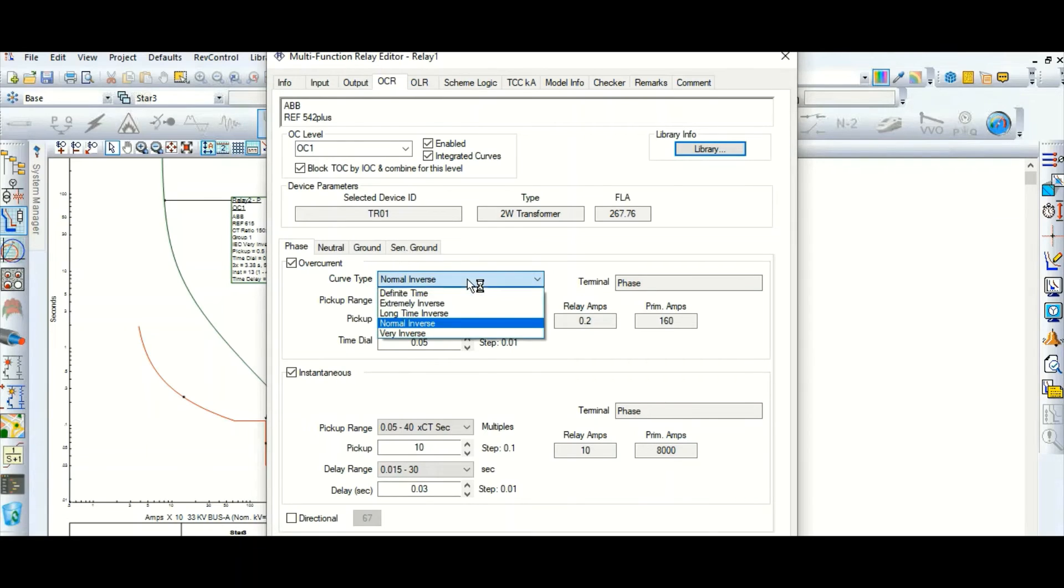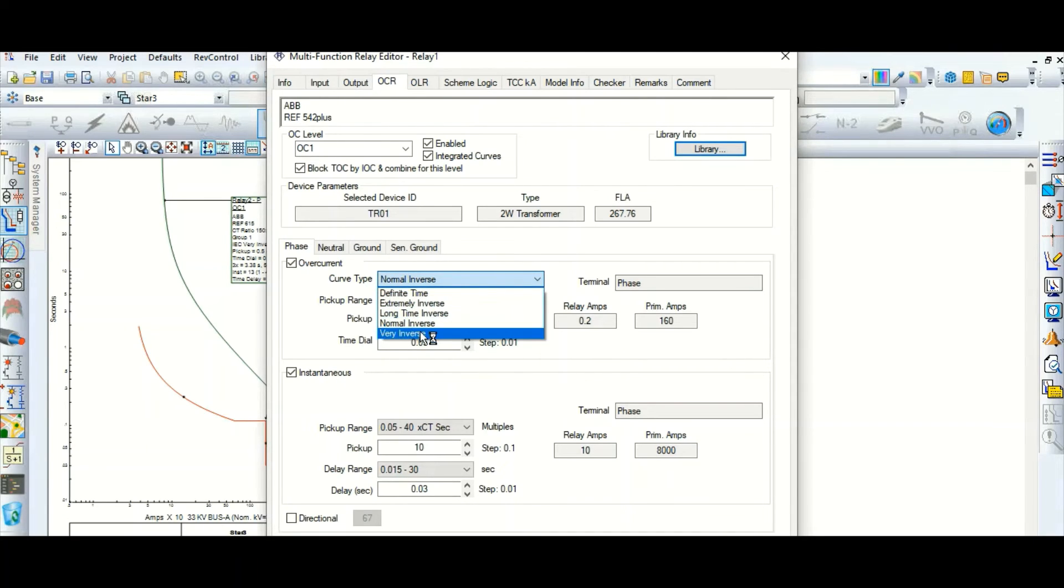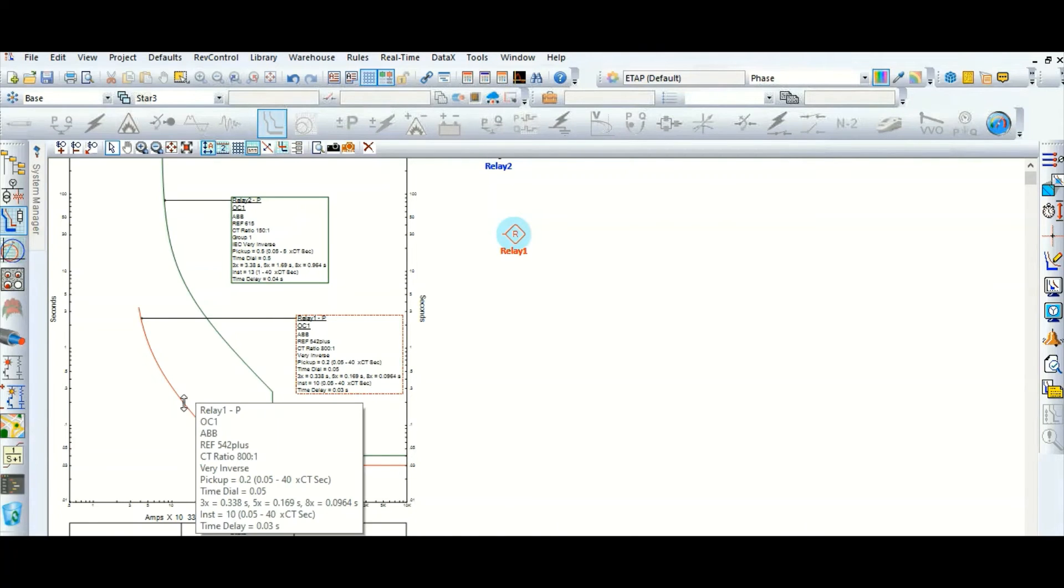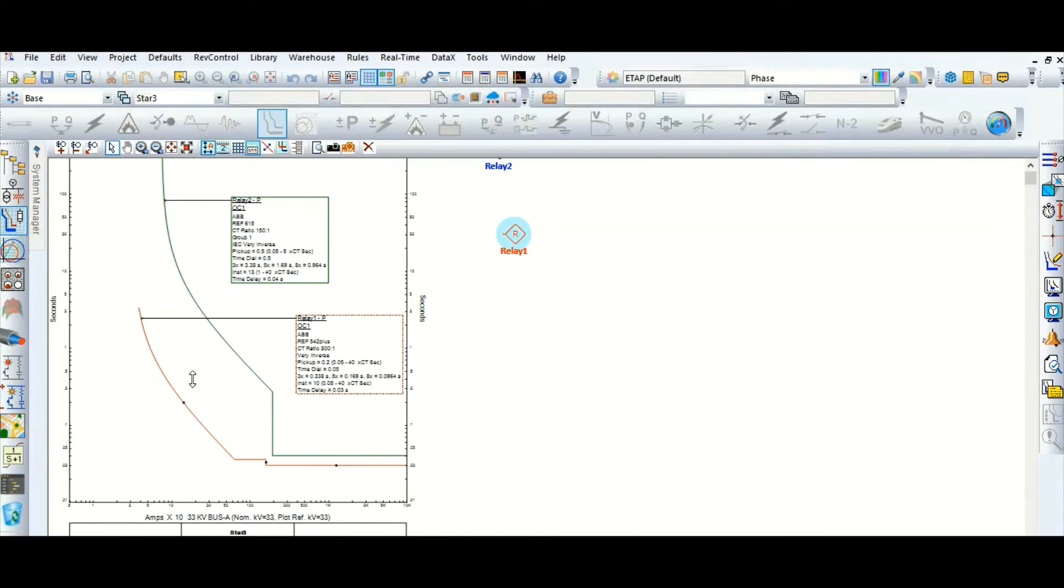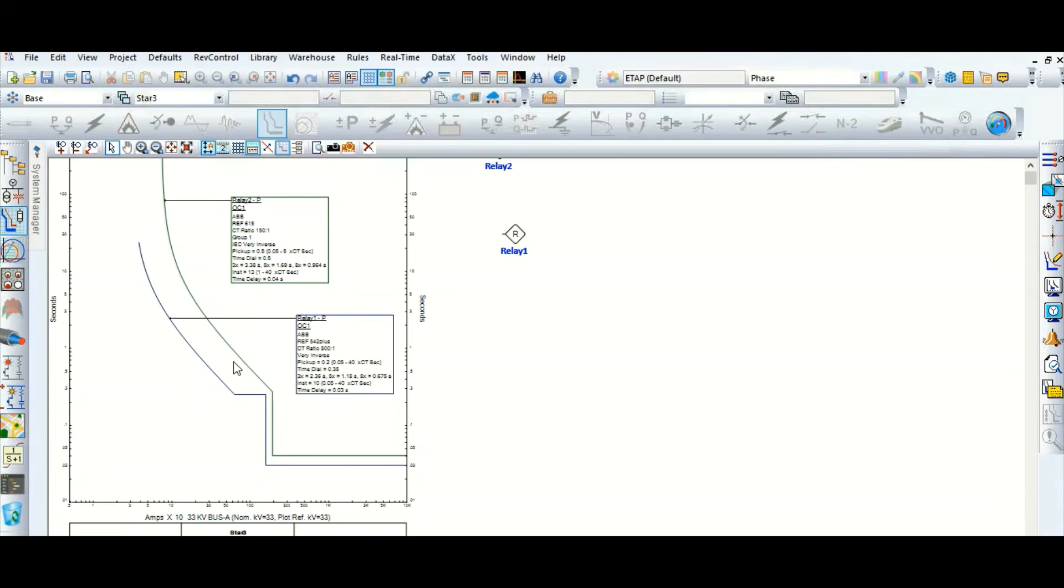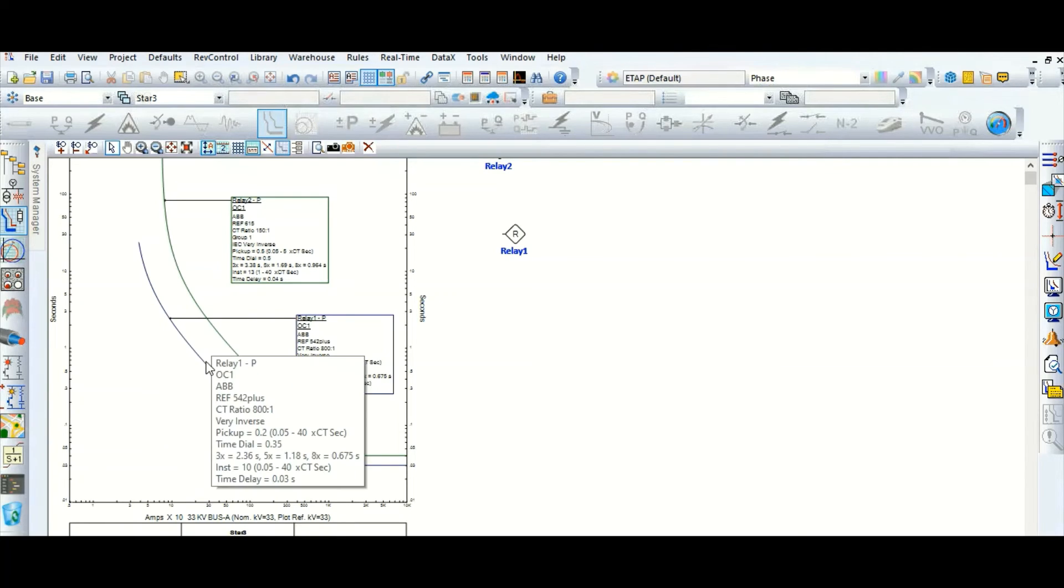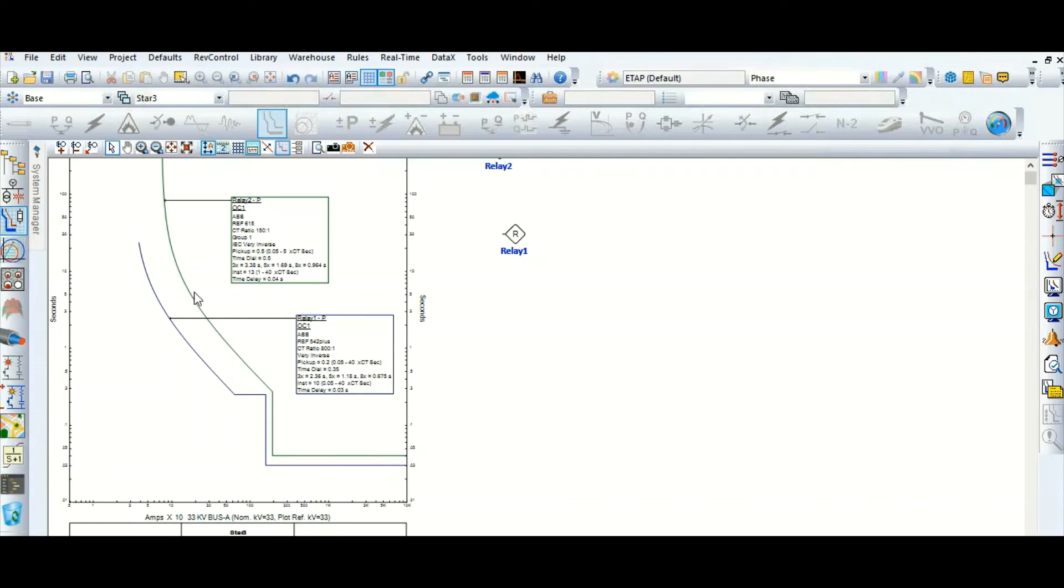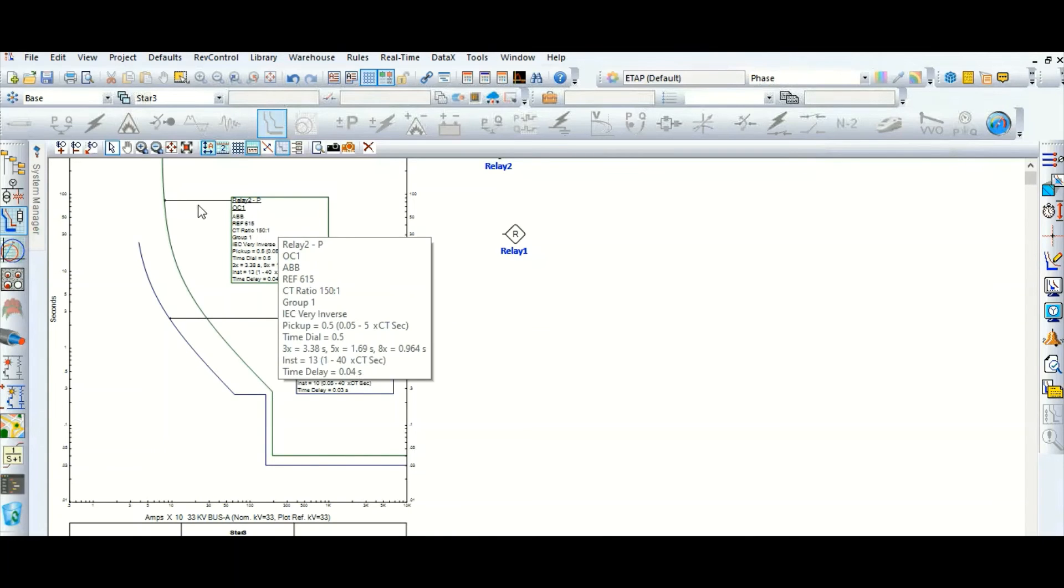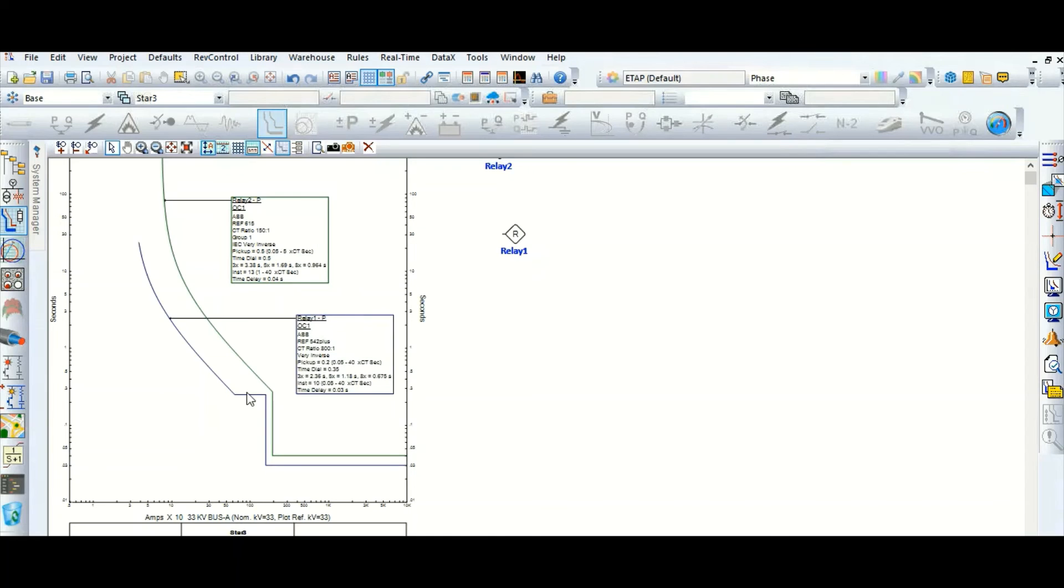To very inverse. Now if we want to coordinate with this relay, definitely there is coordination, protection coordination, because this downstream transformer secondary side relay will pick up first, and then this is the backup protection. Transformer HV side relay will pick up in case of any fault in the LV side.